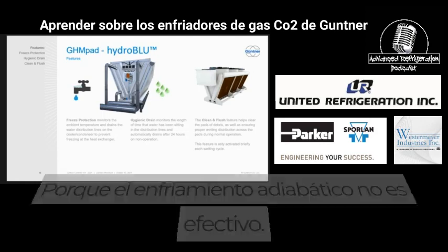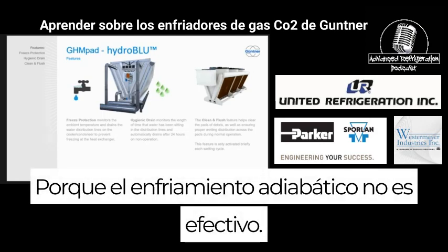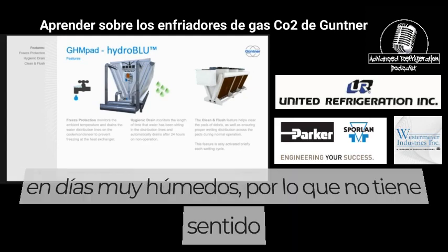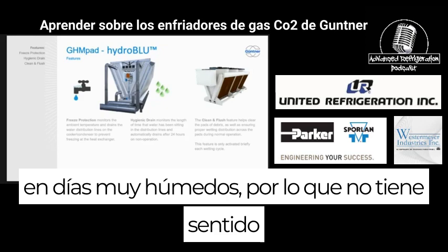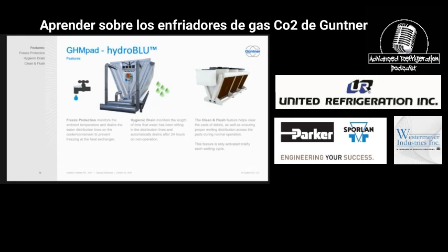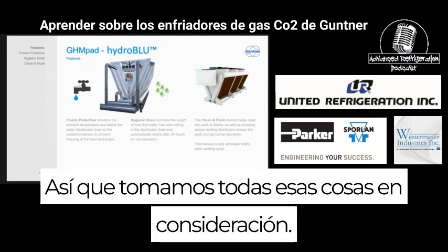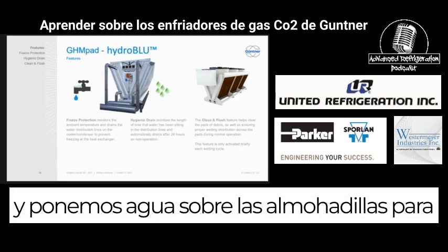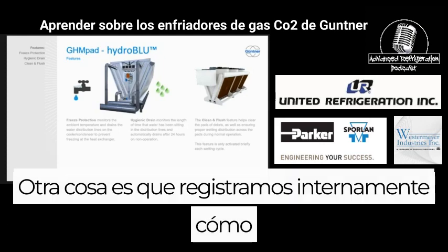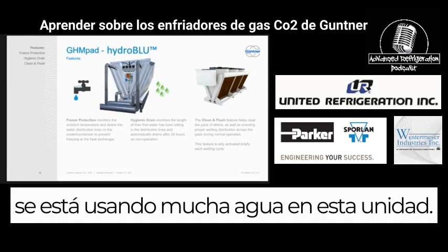on days that it's less humid, because adiabatic cooling is not as effective on very humid days. So there's no point in using water, but on dry days, it's very effective. So we take all those things into consideration and we put water across the pads to make them as efficient as possible. Another thing is we do record internally how much water is being used in this unit.